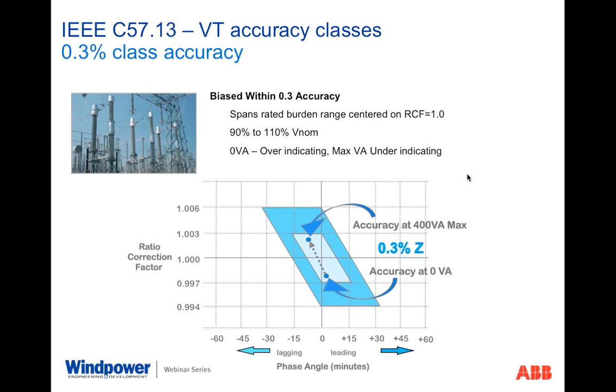So if I had zero burden connected to the VT, I would be operating just within the 0.3 accuracy class, and I would be reading high by almost 0.3% high on the voltage reading. As you load that VT up, just like a power transformer with regulation, you're going to start dropping voltage relative to the output. So the more VA I put on it, the more load I put on it, the more it's going to be approaching 1.000 or perfect accuracy.